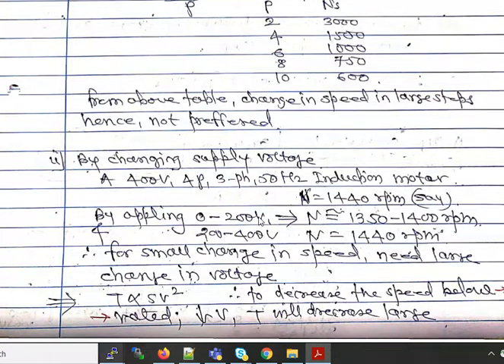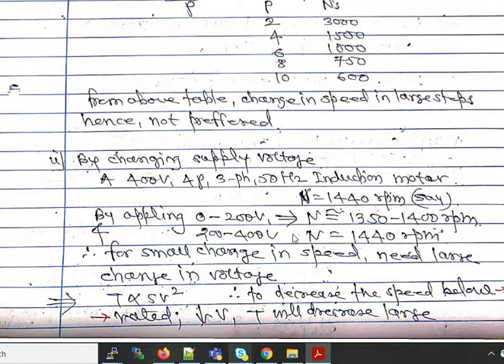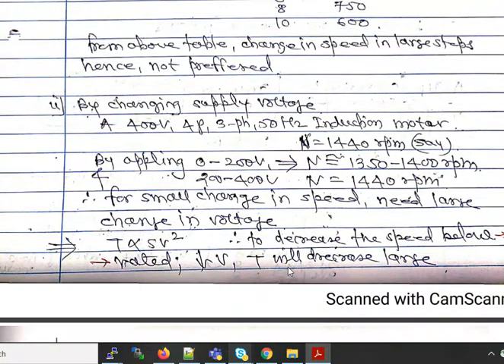Now let us see speed control by changing the supply voltage. When the applied voltage is reduced to 50 percent, the motor achieves about 80 to 90 percent of its speed. To achieve the remaining 10 to 20 percent of speed, we have to increase the voltage from 50 percent back to 100 percent. Therefore a small change in speed requires a large change in voltage.